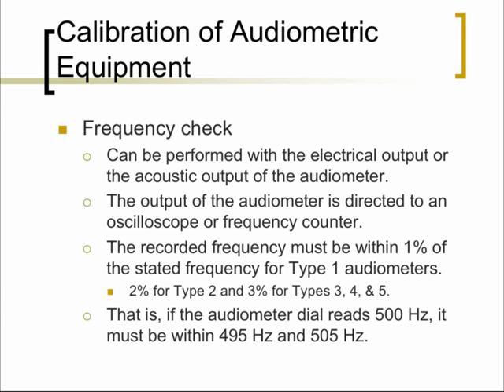For frequency calibration, you check whether the frequency is calibrated for the different buttons used. The recorded frequency should be within 1% of the stated frequency for type 1 audiometers (diagnostic audiometers used in clinical comprehensive evaluations). For type 2 and 3 audiometers used for screening, the permitted frequency deviation is within 2% of the stated frequency. For example, if an audiometer reads 500 Hz and is a type 1, the recorded frequency should be within 495 Hz to 505 Hz.